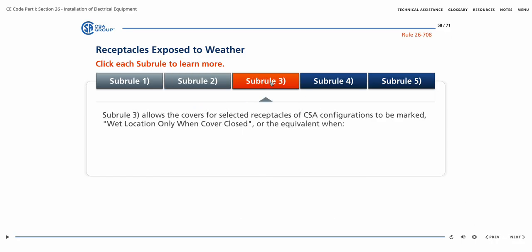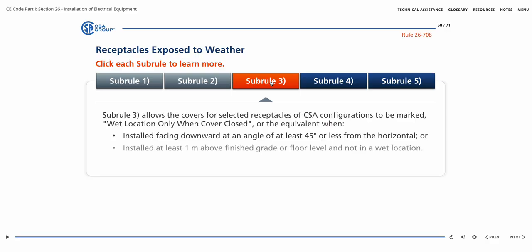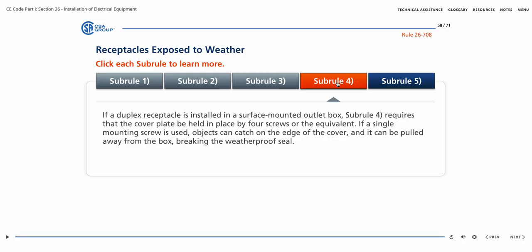Subrule 3 allows the covers for selected receptacles of CSA to be marked wet location only when cover closed, or the equivalent, when installed facing downward at an angle of at least 45 degrees or less from the horizontal, or installed at least 1 meter above finished grade or floor level and not in a wet location. If a duplex receptacle is installed in a surface-mounted outlet box, Subrule 4 requires that the cover plate be held in place by 4 screws or the equivalent. If a single mounting screw is used, objects can catch on the edge of the cover, and it can be pulled away from the box, breaking the weatherproof seal.